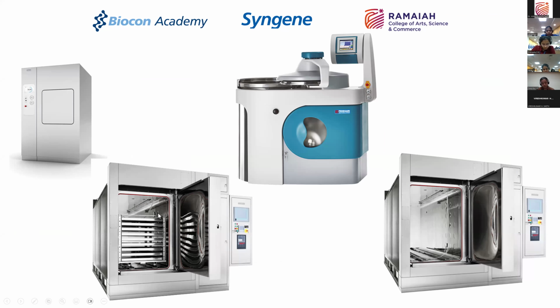The validation port is here. So there's one opening here. You will place it near the drain. Everywhere you will place those spores. Now your steam is flowing from the top. It is trying to sterilize the whole load and going out.